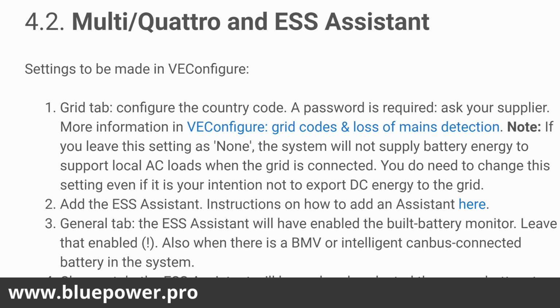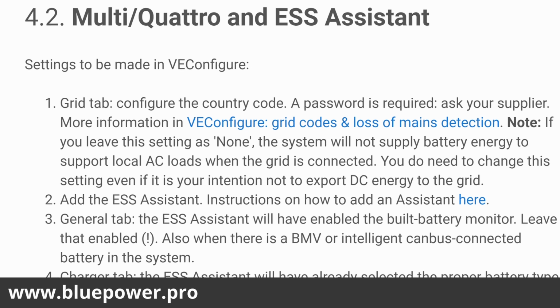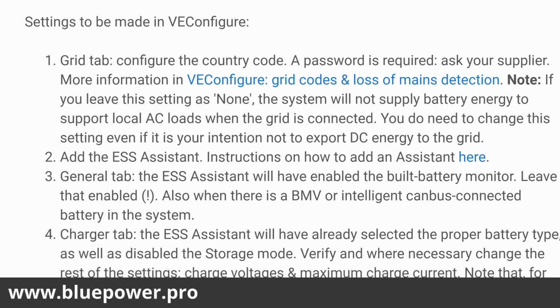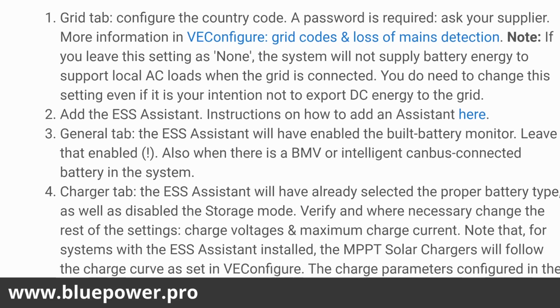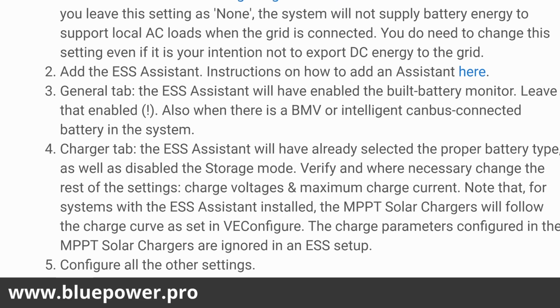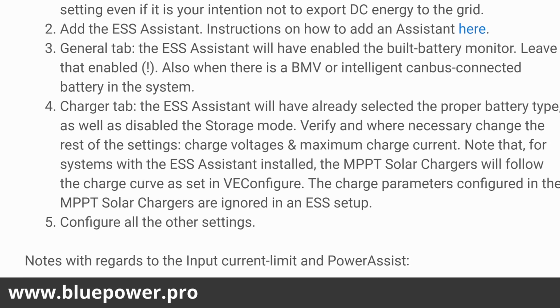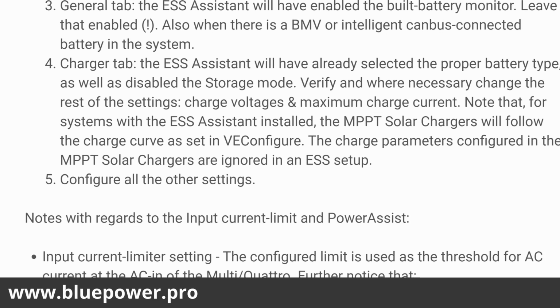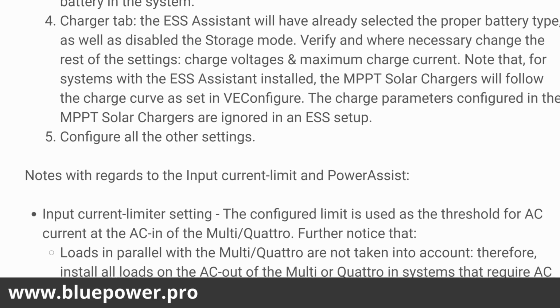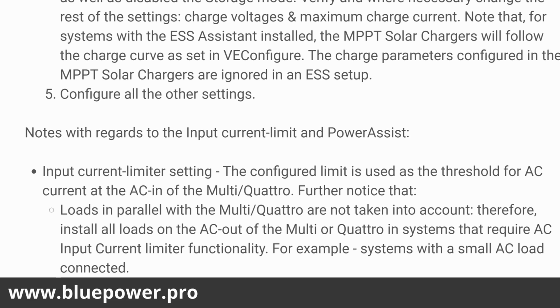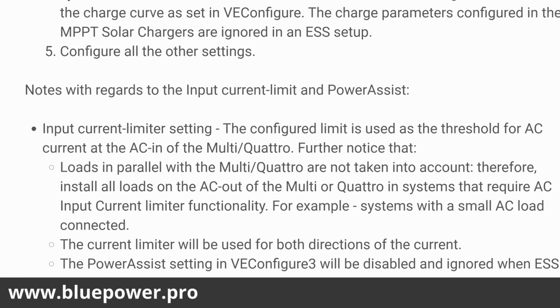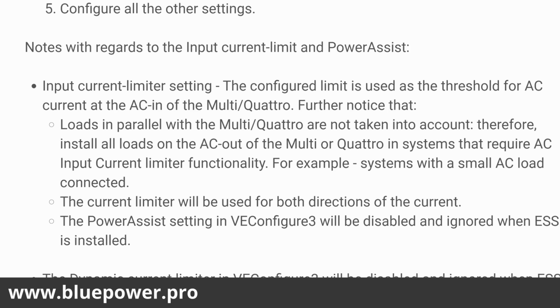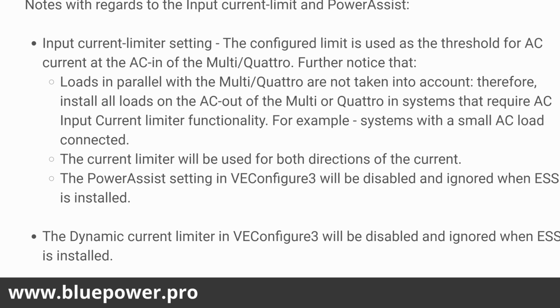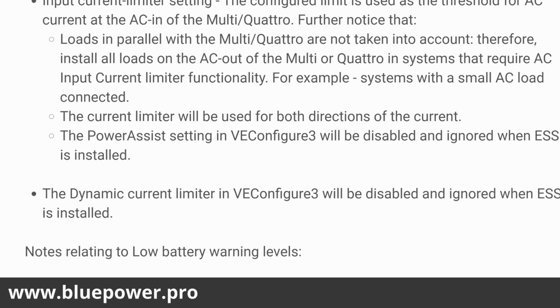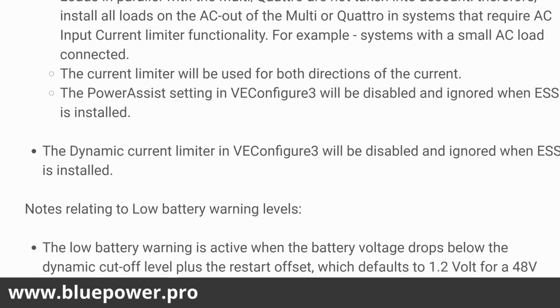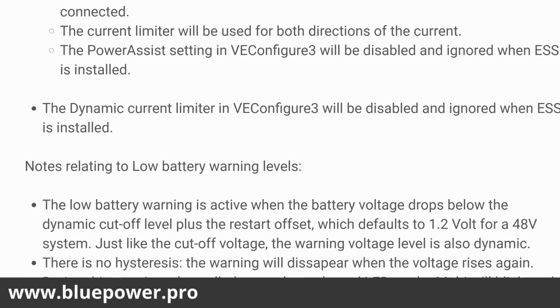So Quattros and the ESS Assistant. Settings have to be configured on the Multiplus inverter. That's under your grid tab. You have to select the corresponding grid code for the area that we're installing, and that's South Africa for us. We've got a Multiplus-II that you're installing, so you'll select the South African grid code. Other areas require other grid code connections, but that depends on where you're installing. But generally for South Africa, on the Multiplus-IIs or Quattro-II inverters, you can just set it to the South African grid code. And on the older Multiplus or Quattro inverters, you're going to have to set it to whichever grid code is recommended in the manual. That's usually on other.